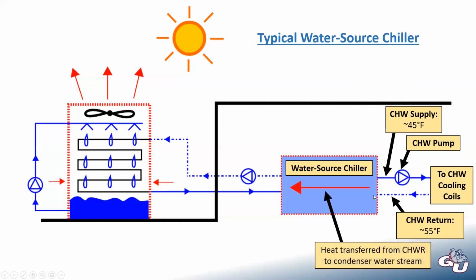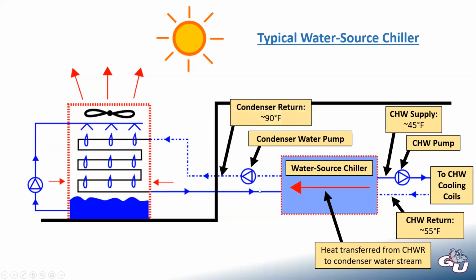But in our water source chiller, we're pulling heat out of our warmish chilled water and then using a DX refrigeration process to move that heat into this water stream on this side. We have to have another pump because that water is not going to move on its own. So we have a condenser water pump that's moving the condenser water loop on this side of our chiller. Our condenser return, which you can see is moving towards the cooling tower over here, is at about 90 degrees. Comparatively, that's a lot warmer than what's going on our chilled water side. So we're sending 90-degree water to our cooling tower or fluid cooler.